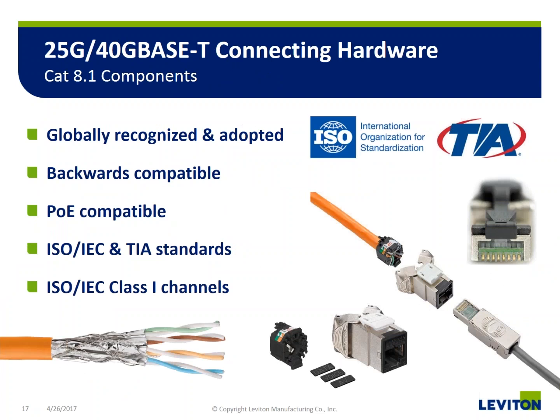Let's look specifically at some of the connectivity options for Category 8. Keep in mind that with Category 8, there's two different types of options, specifically the Category 8.1 components, which are based on the RJ45 solution. This is a globally recognized and adopted platform, backwards compatible with existing copper cabling systems, PoE compatible. It's recognized by both IEC and the TIA standards, for those that adhere to some of the American standards, wherever you are in the world. With ISO IEC, it's called a Class 1 channel.